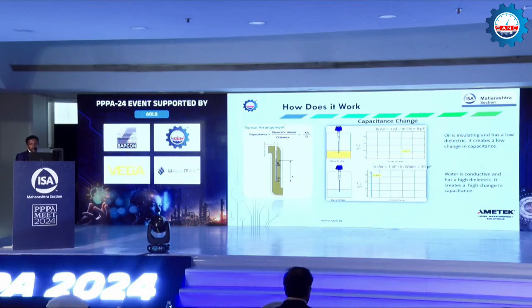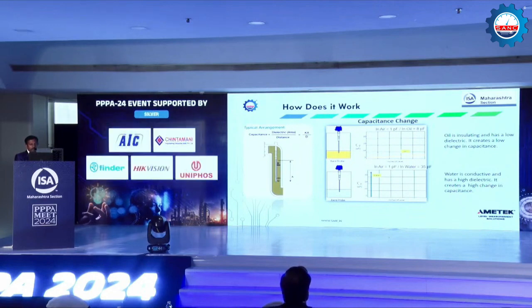So 8 is 0 percent, and 35 is maybe 50% as per this device. This device range is 50%, and we also have 30% and 80% ranges. So we calibrate it from 0 to span. 8 is 0, 35 is span. This is just an example. In the real world, we'll get different picofarad values depending on the pipe size and characteristics.